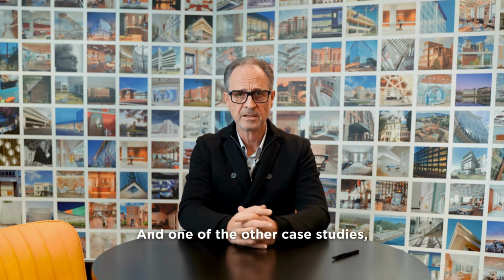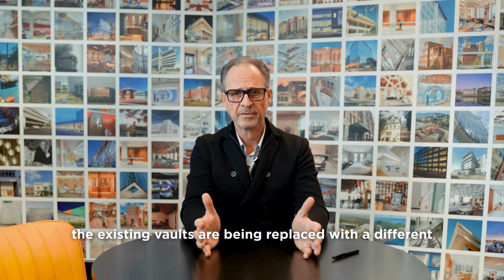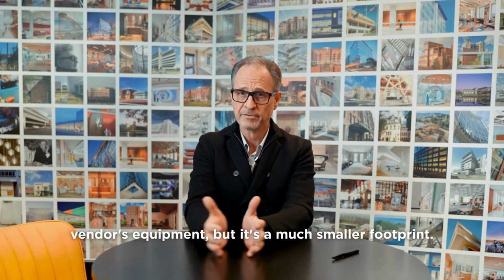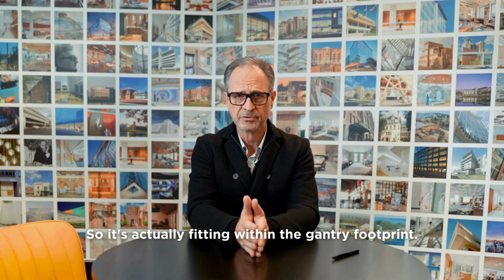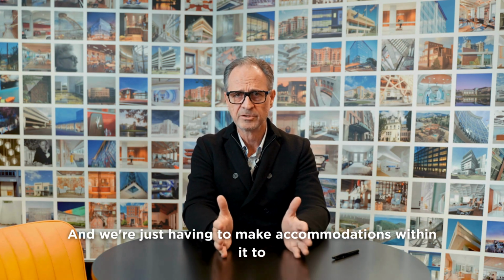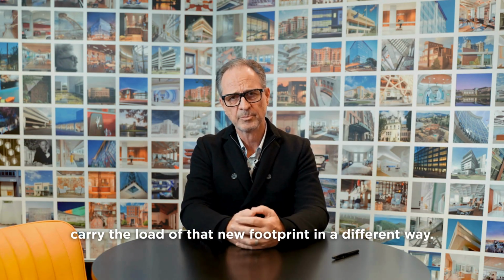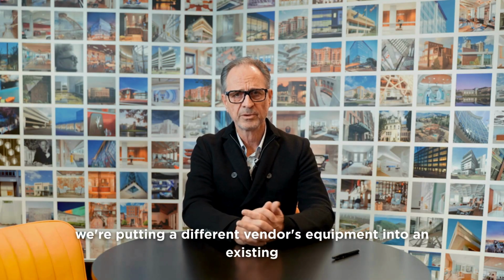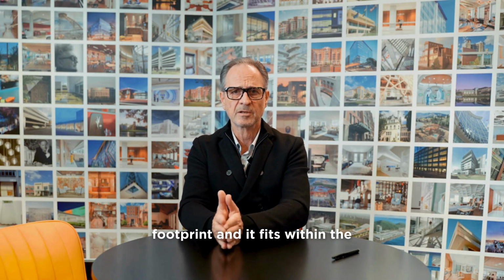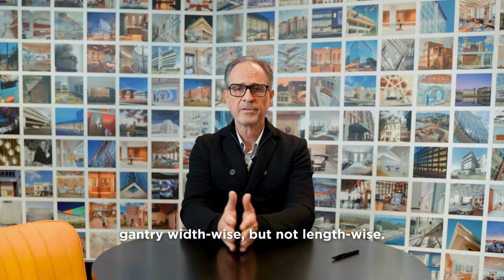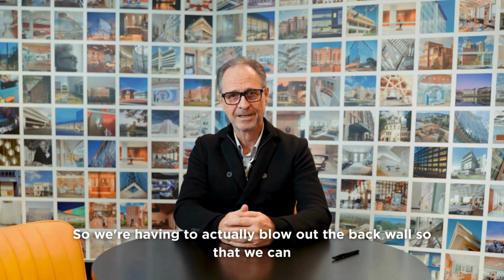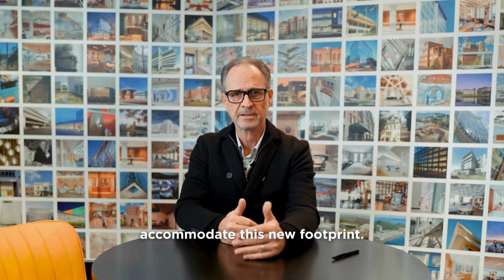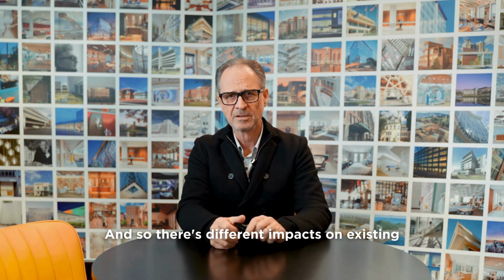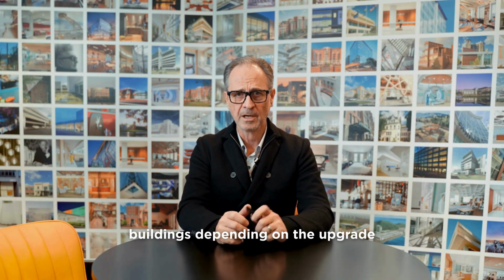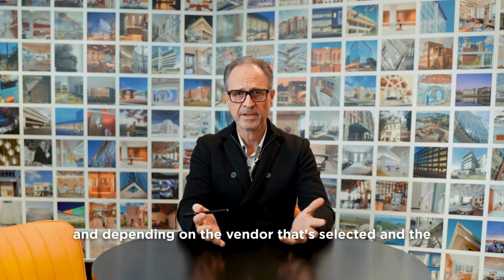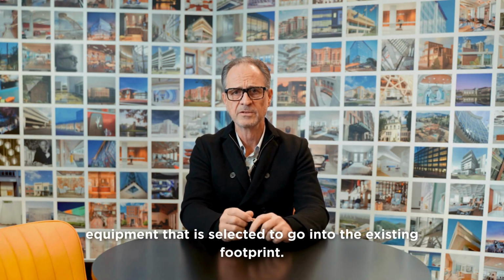In one of the other case studies, the existing vaults are being replaced with a different vendor's equipment, but it's a much smaller footprint. So it's actually fitting within the gantry footprint. And we're just having to make accommodations within it to carry the load of that new footprint in a different way. In one of these cases, we're putting a different vendor's equipment into an existing footprint, and it fits within the gantry widthwise, but not lengthwise. So we're having to actually blow out the back wall so that we can accommodate this new footprint. And so there's different impacts on existing buildings depending on the upgrade and depending on the vendor that's selected and the equipment that is selected to go into the existing footprint.